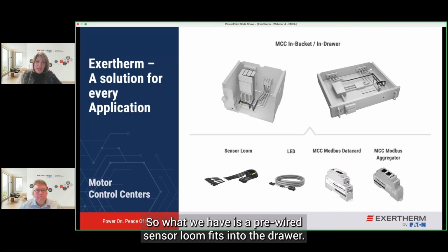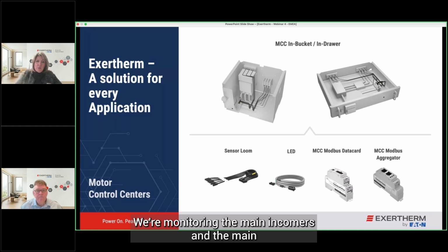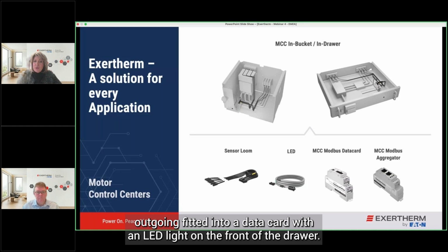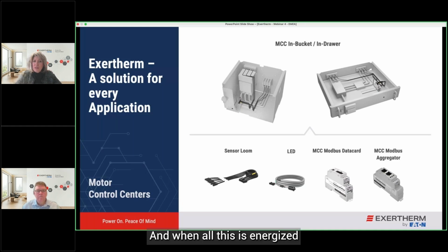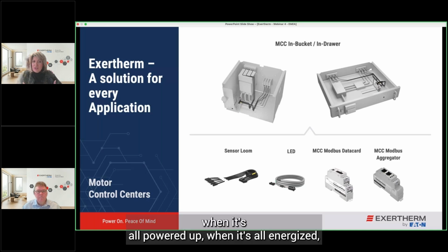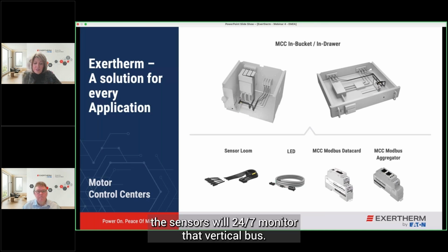What we have is a pre-wired sensor loom that fits into the drawer. We monitor the main incomers and main outgoing, fitted into a data card with an LED light on the front of the drawer. When it's all energized and powered up, the sensors will monitor that vertical bus 24/7.